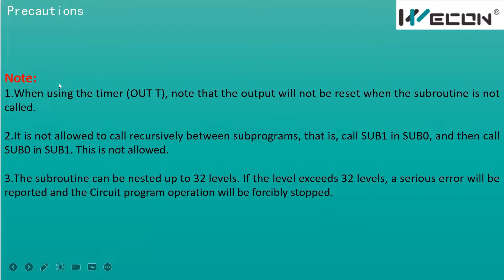Here are some points we need to pay attention to. First, when we're using a timer in a subroutine, the timer output will not be reset when the subroutine is not called.